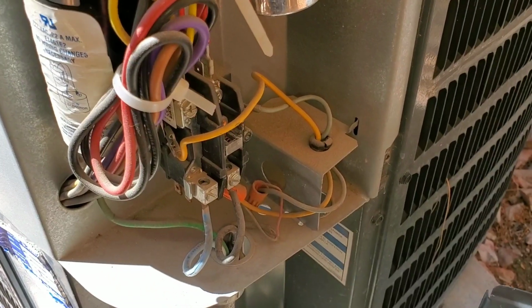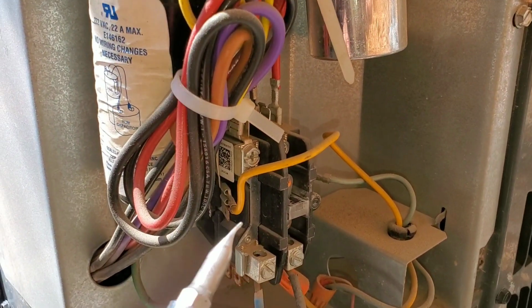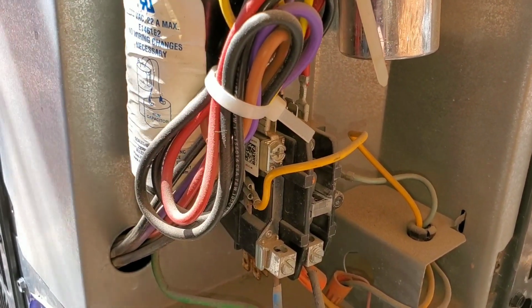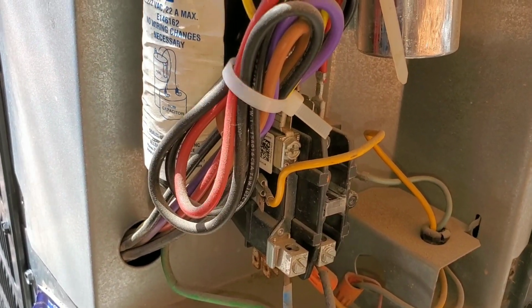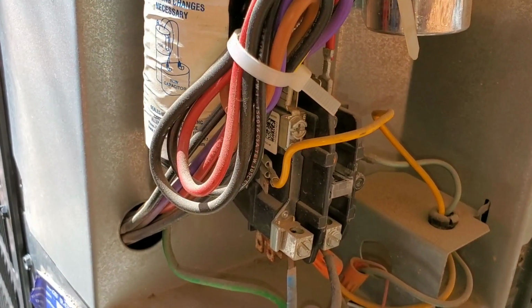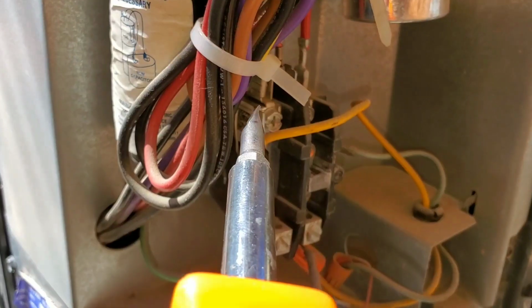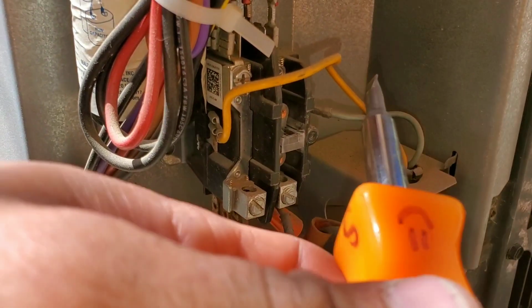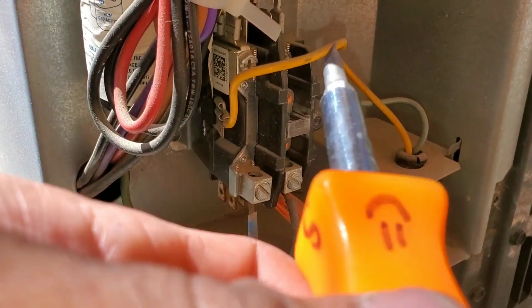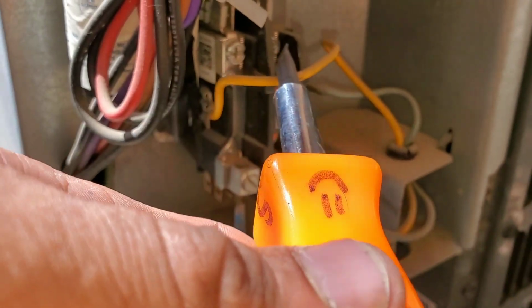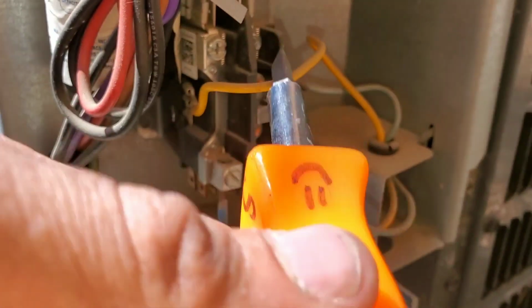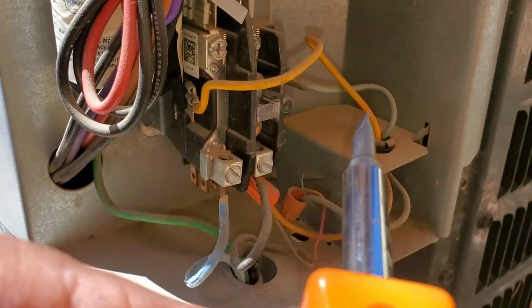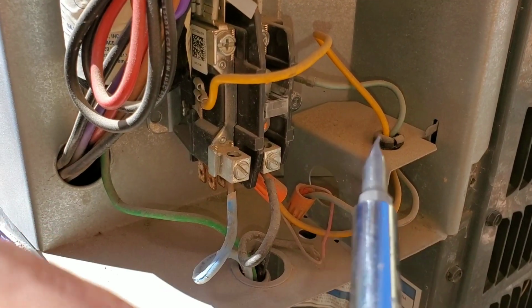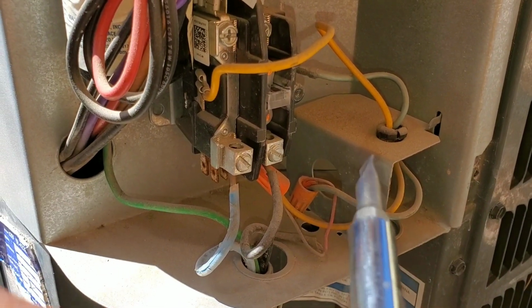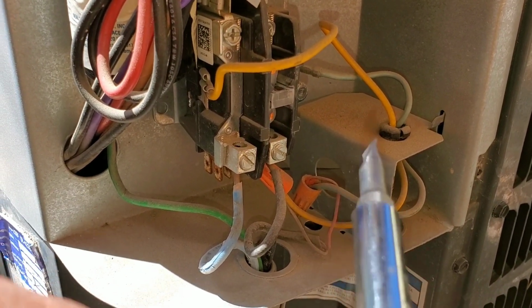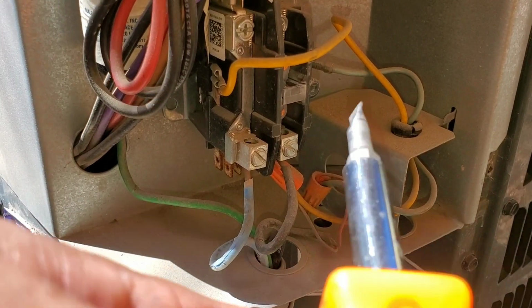Here, I remove my panel. This is going to be my contactor. Be very careful when you're working on electrical. Right now you have 240 volts coming in, and you have your low voltage wires, which are your yellow and your blue. The colors may vary depending on your system. This is your low voltage. This is what is going to engage when you get 24 volts energizing your contactor. So what I'm going to do is manually engage my contactor.